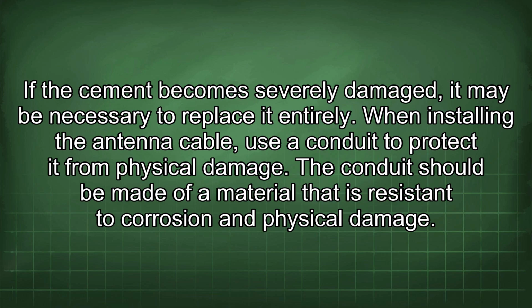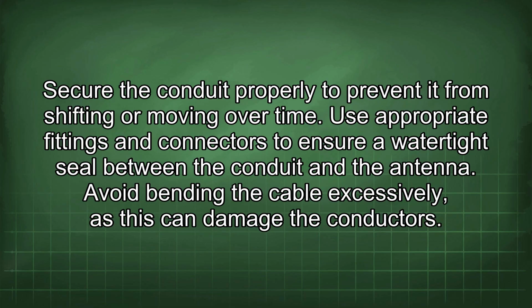When installing the antenna cable, use a conduit to protect it from physical damage. The conduit should be made of a material that is resistant to corrosion and physical damage. Secure the conduit properly to prevent it from shifting or moving over time. Use appropriate fittings and connectors to ensure a watertight seal between the conduit and the antenna.